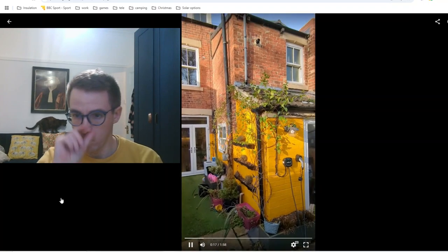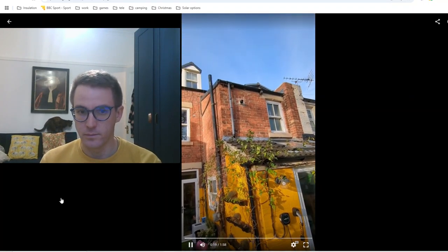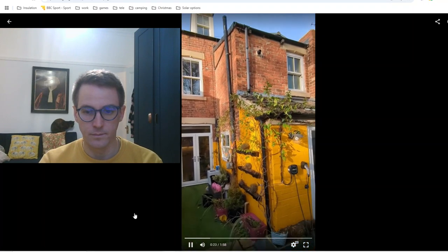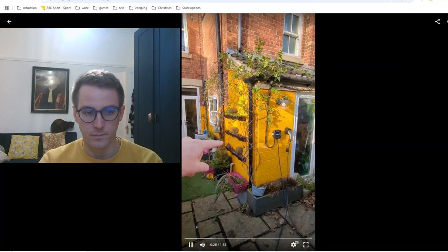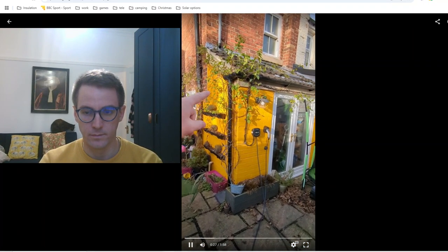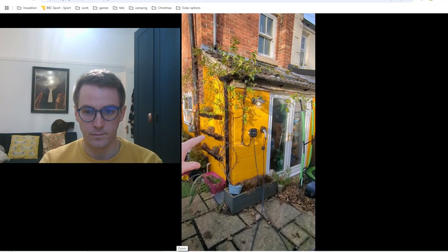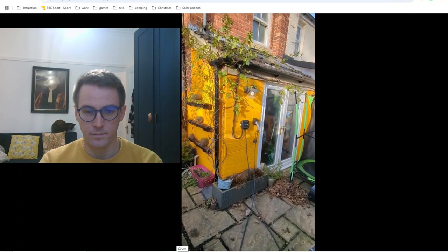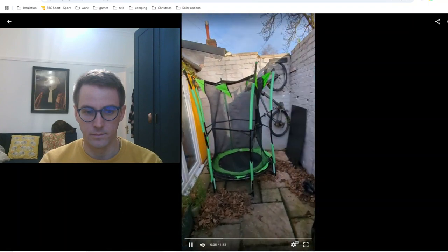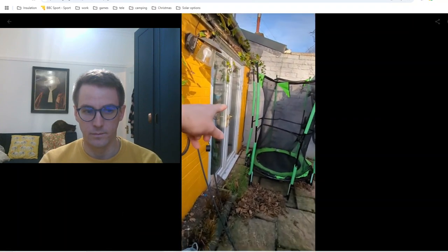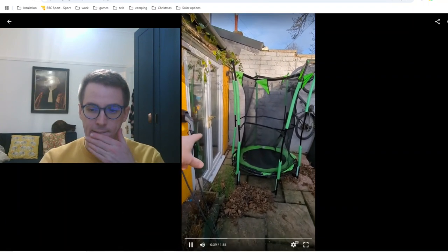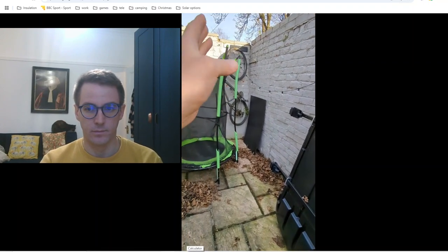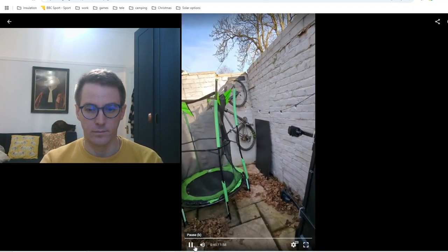It's solid wall, though actually it's not so clear from the brickwork, so it might be unfilled cavity, not 100% sure. But the heat pump is proposed to go here where these planters are. We'll have to remove those, of course, and then we get the condenser drained straight down in here. We didn't quite have the clearances here because these don't open, but unless we screwed them in, you'd have to have 1.5 metres away from the door to have a propane heat pump.